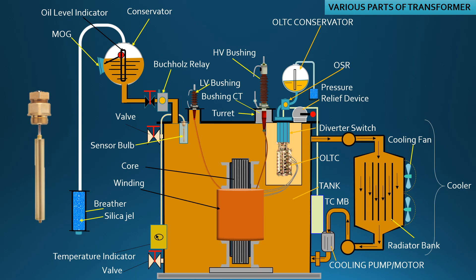Expansion and contraction of oil or vapor inside the sensor bulb according to the temperature of the oil or winding is taken to calibration equipment to operate WTI, OTI and issue tripping of circuit breaker when temperature reaches beyond preset value.